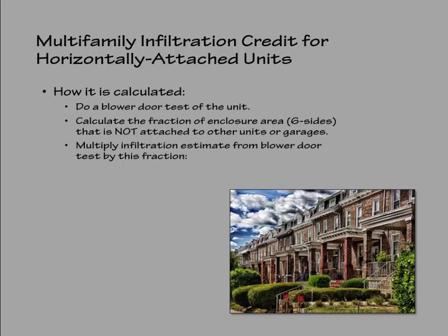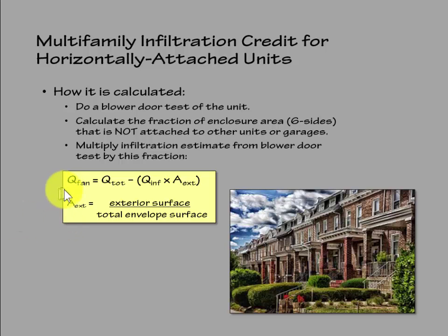We multiply the infiltration estimate from the blower door test by this fraction, and that shows in the equation right here. Q fan, or the amount of mechanical ventilation we need, is equal to Q tot minus Q inf for the infiltration. This is for detached, but when we have horizontally attached, then we have this value here, A sub exterior, or A sub X, which is equal to the exterior surface over the total envelope surface. Again, the exterior surface over the total envelope surface.